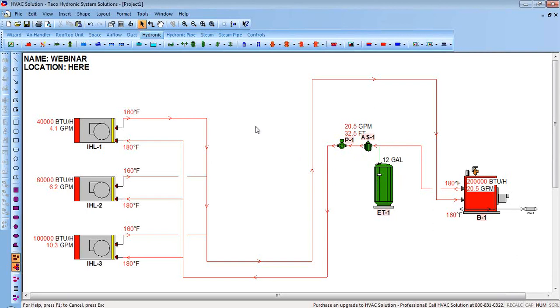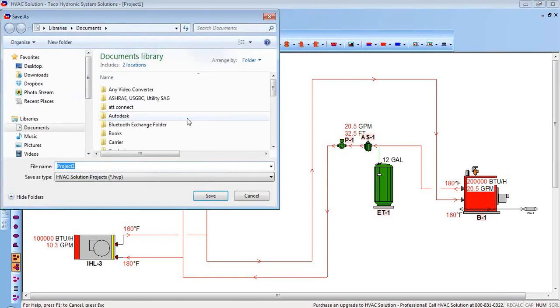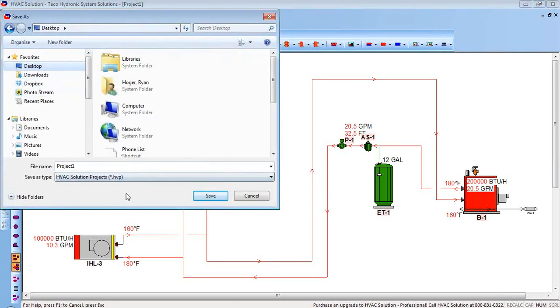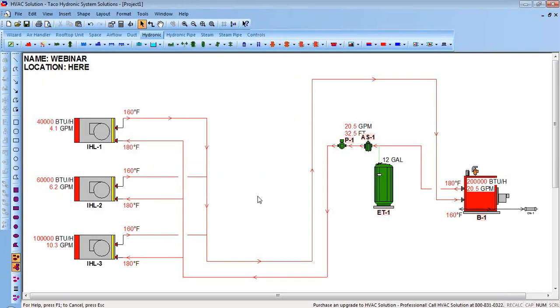The pump is always downstream of the expansion tank — we always pump away from the expansion tank, never into it. At this point I want to save my drawing — File, Save As, put it on my desktop as 'Project number one.' Now let's run some reports to see what they look like, and then we'll come back and draw some other things.